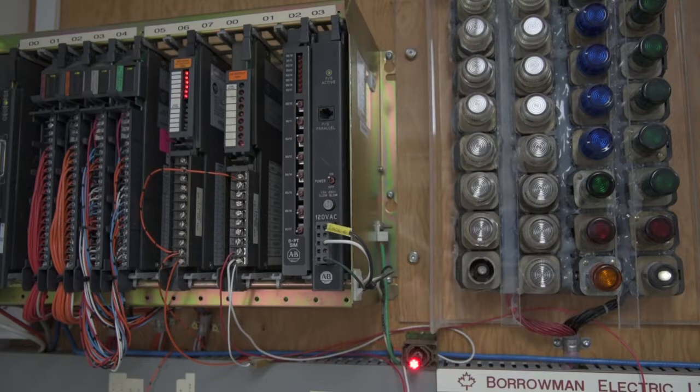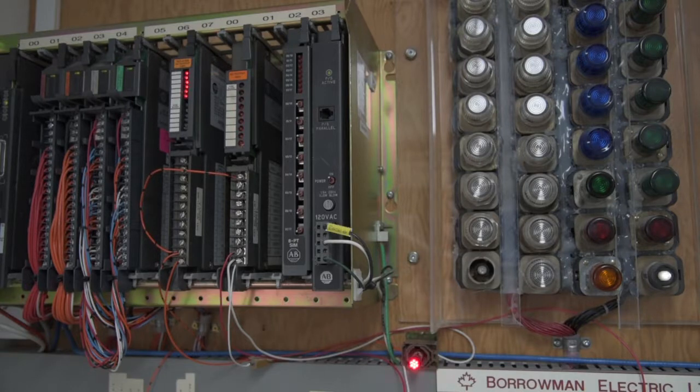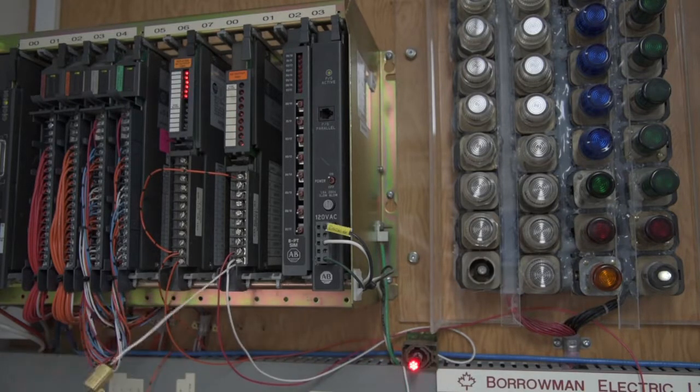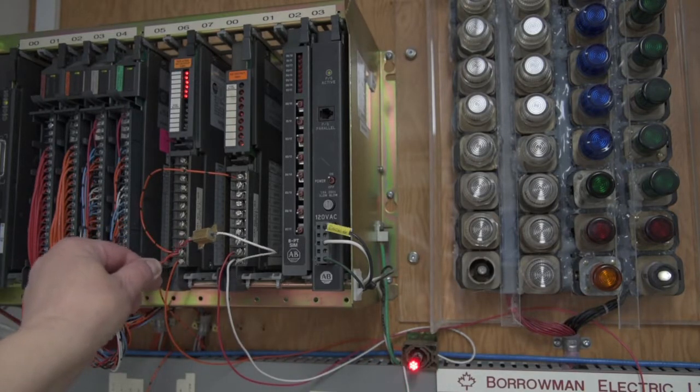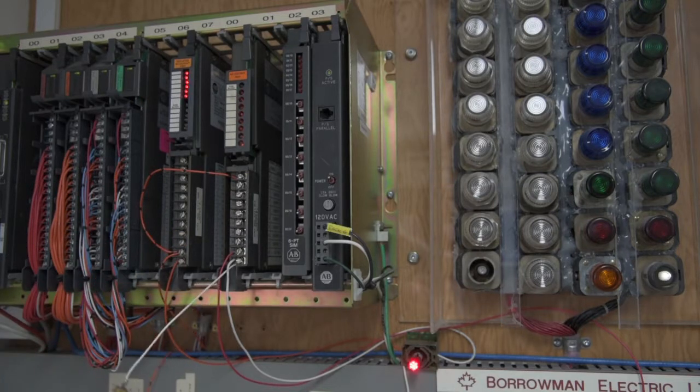Now, the Allen-Bradley specs say put a 2.5K 10-watt resistor between neutral and your output.